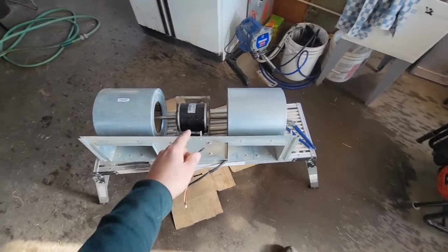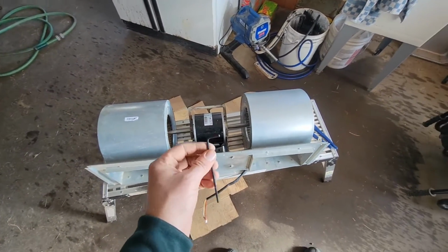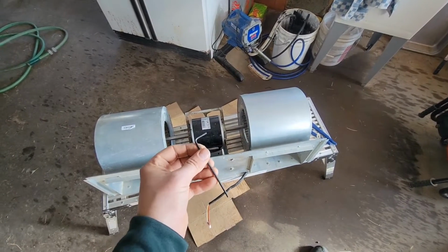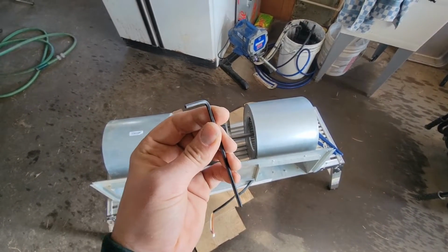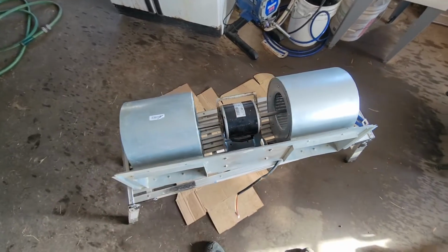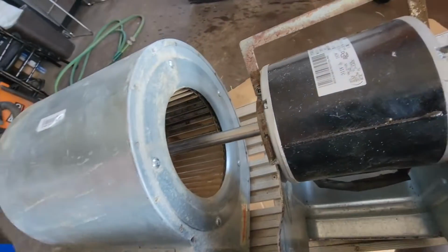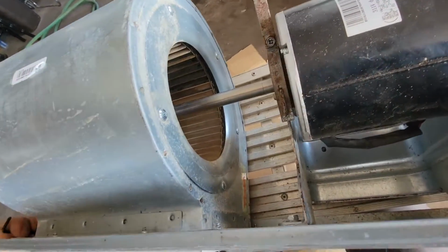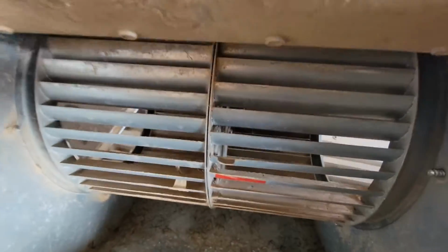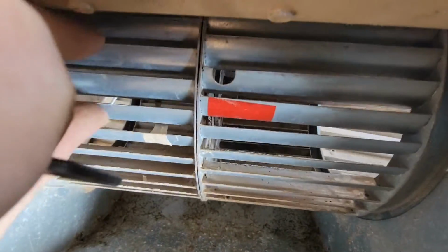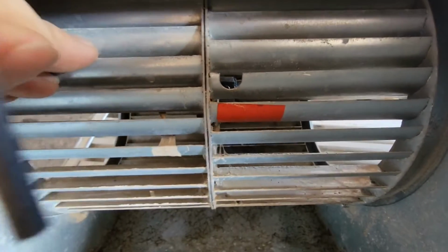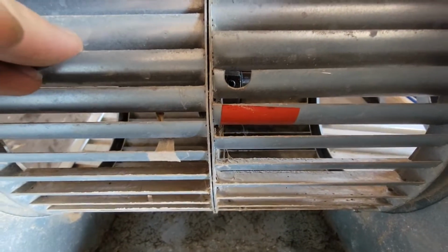We're going to go to samsunghvac.com. I am going to give you a couple tips on installing this motor right here in this Samsung ducted air handler. Now this right here is an Allen tool, and this is so I can loosen the set screw for this blower wheel. The way I do that is I move the wheel to where I can see that Allen screw.